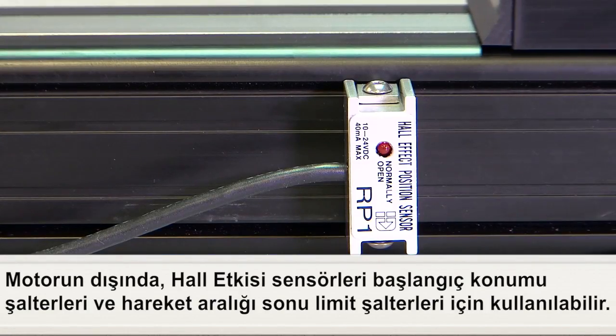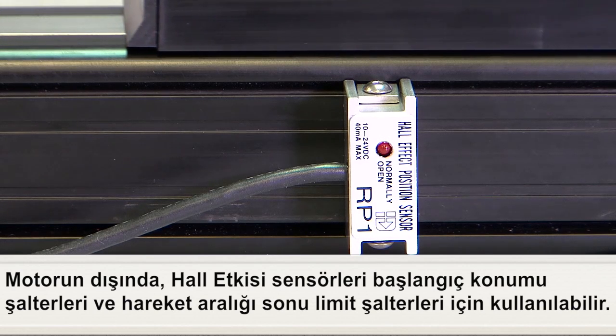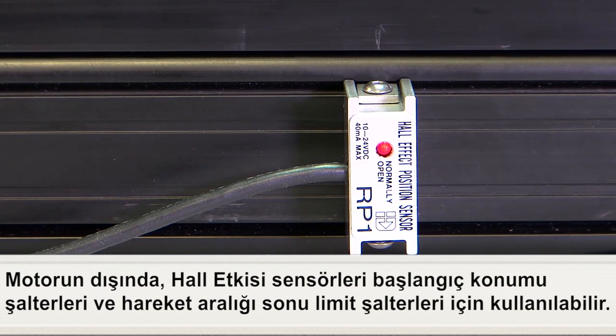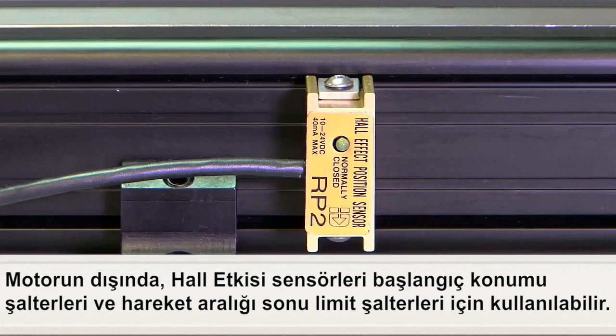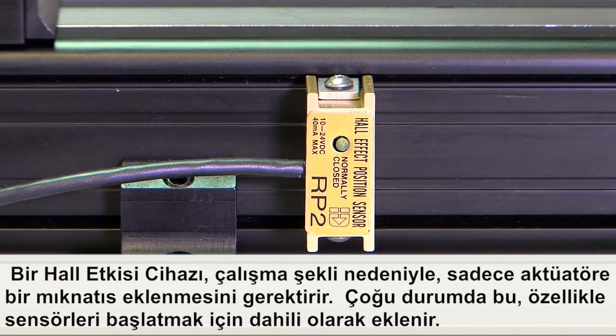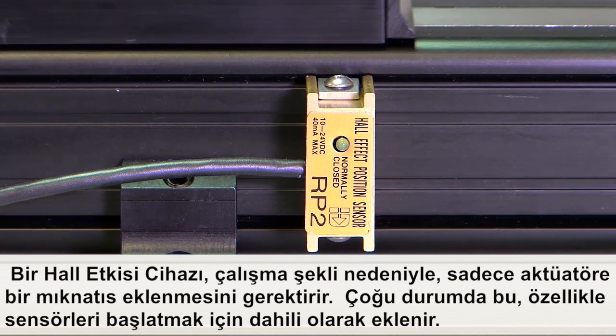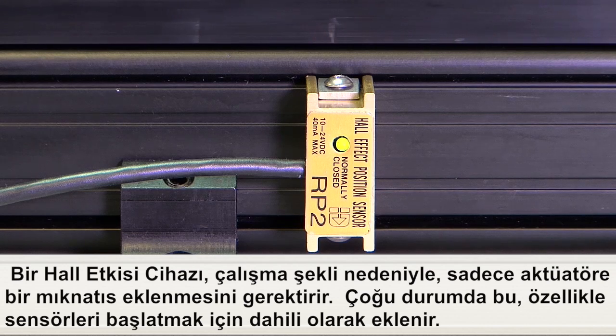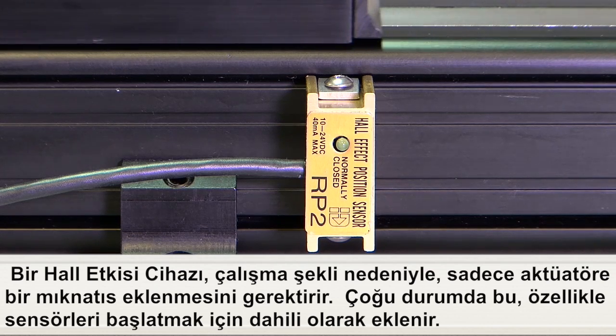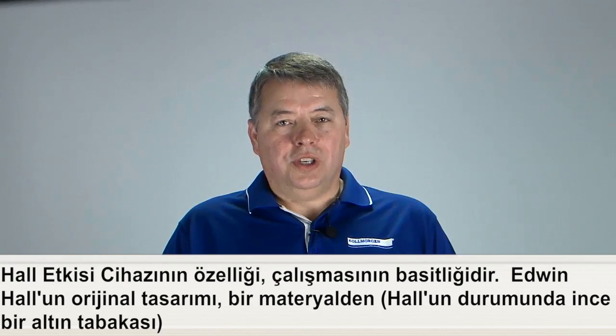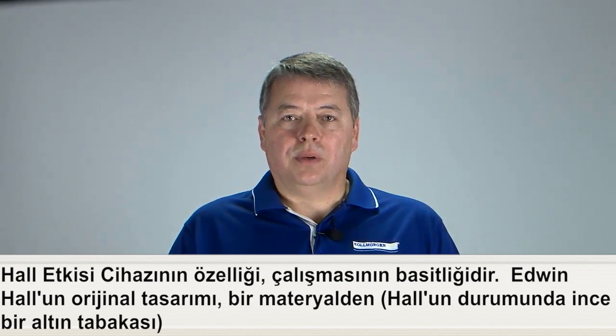Outside of the motor, Hall effect sensors can be used for home switches and end of travel limit switches. Because of the way the Hall effect devices work, it requires only adding a magnet to the actuator. In most cases, this is added internally, specifically to trigger the sensor. The genius of the Hall effect device is how simple it works.